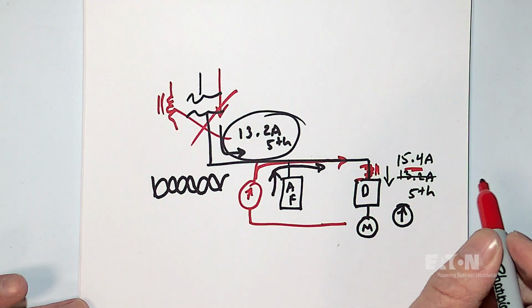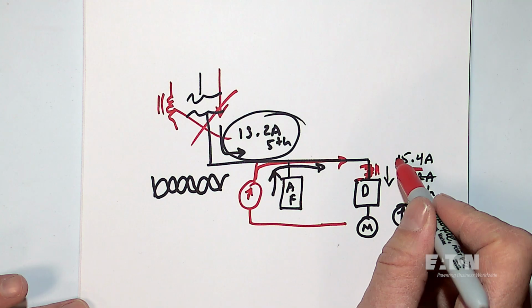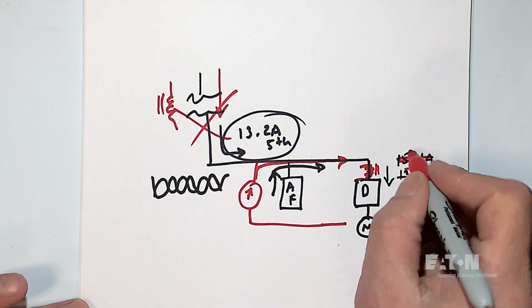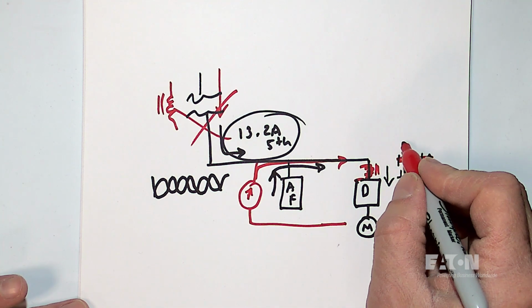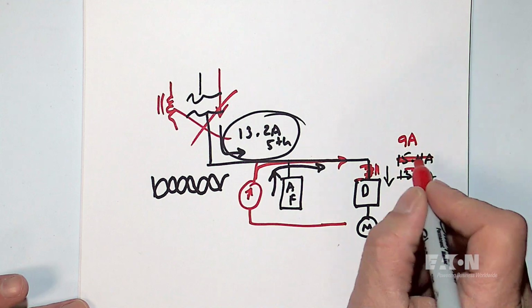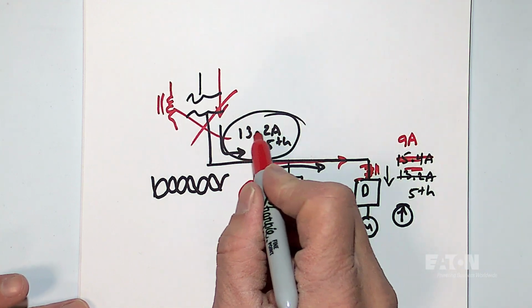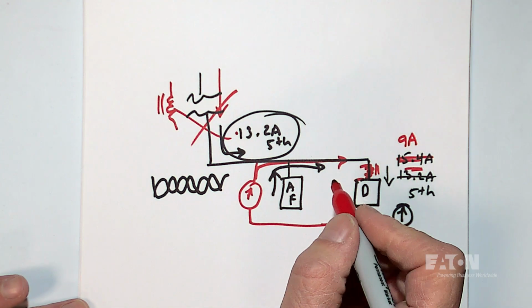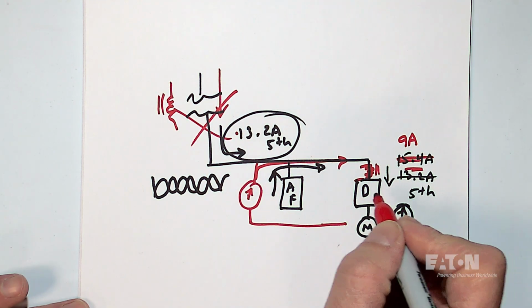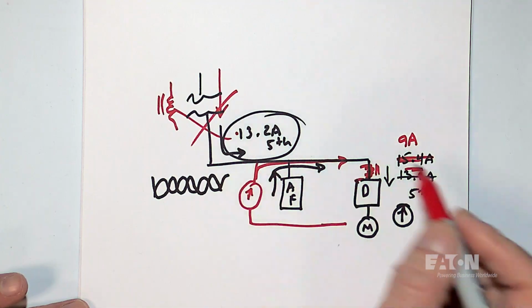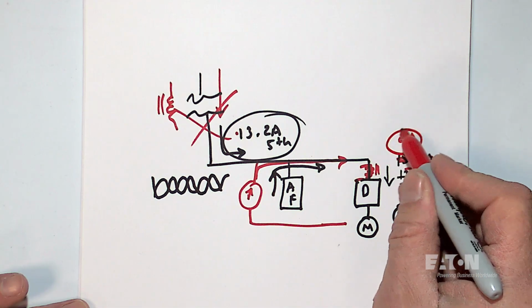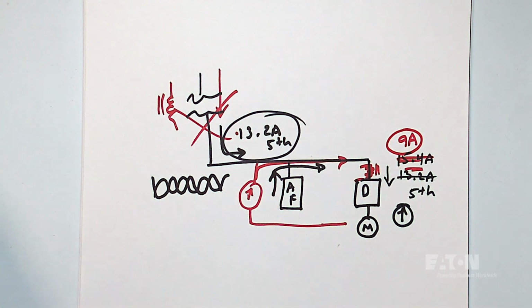So what I did in the second example was add in this line reactor here, and by adding a line reactor here, we first of all reduce this down in the beginning to something less than 9 amps. And then when we put the active filter on over here, obviously this went to 0 on this side, but this stayed at about 9 amps.